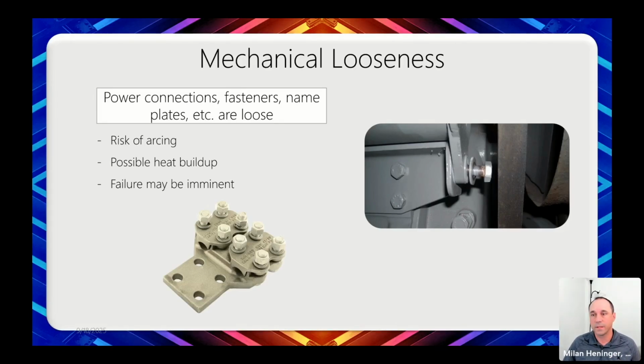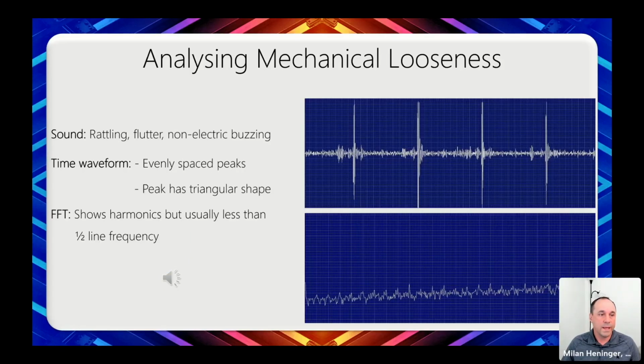When we do the analysis on mechanical looseness, we get this rattling, fluttering, non-electrical buzzing sound. We tend to have very evenly spaced peaks that have a triangular shape, usually, and they're always pointing to the right. And this is the decay. Whatever's loose gets excited by the line frequency. It starts vibrating and then it damps out. And we're seeing that damping as it points to the right.